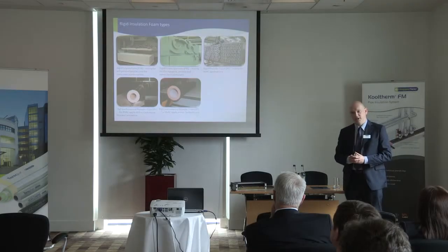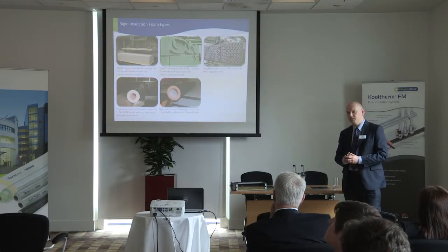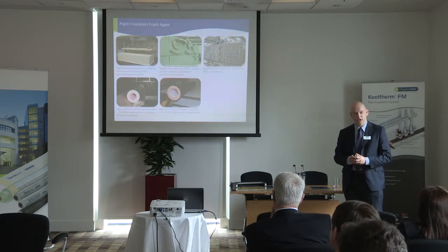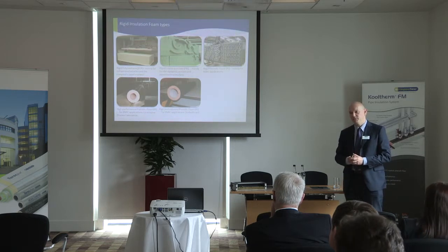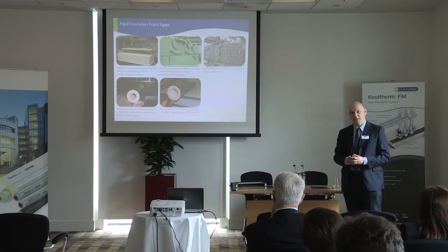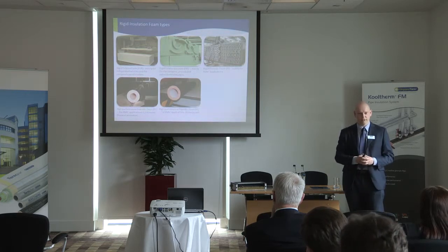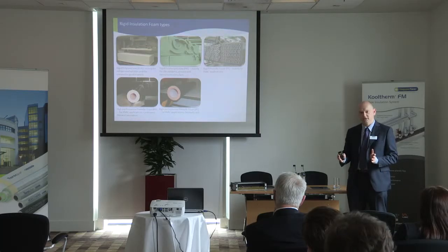Moving on from that, in terms of product development and product technology, you've got the phenolic insulation products, which are a step up again in terms of the thermal performance of products. They are primarily used in HVAC applications, but they can be used in refrigeration as well. Their operating temperature is from -50 up to plus 110 degrees C. So it's quite a range that covers the standard HVAC applications.